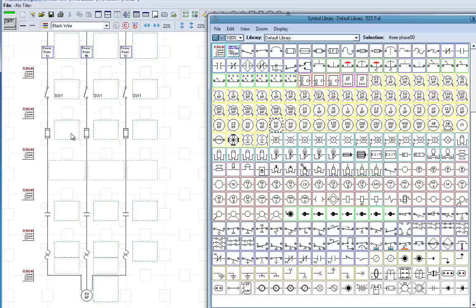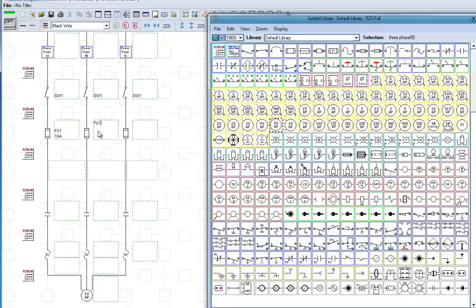Fuse 1, 10 amp. Well, a 10 amp is not going to be quite sufficient for a 50 horsepower motor, obviously. But we'll just leave that for right now. 10 amp.